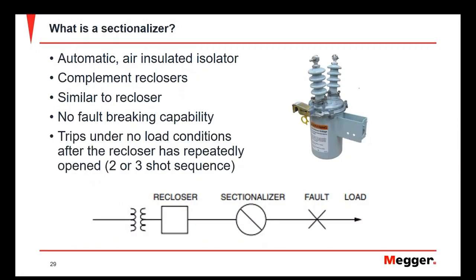In complement to a recloser, a sectionalizer is a device that also has a protective function built in. However, it's not built to function under a fault condition — it's built to open under a no-load condition. After the recloser operates, completes its shot sequence, and locks out, the sectionalizer opens to isolate the rest of the circuit. If designed to do so, the recloser may reset and close back in to restore other branches of the circuit.